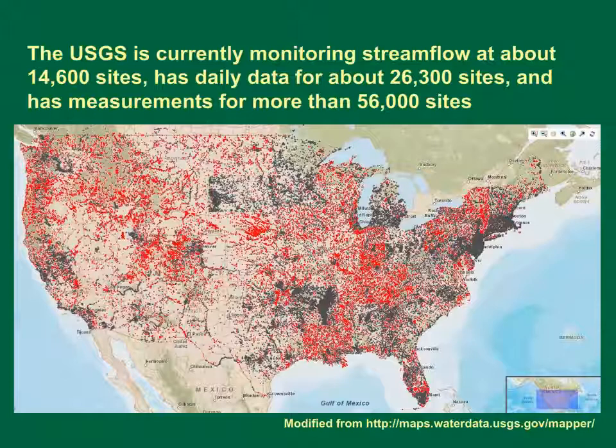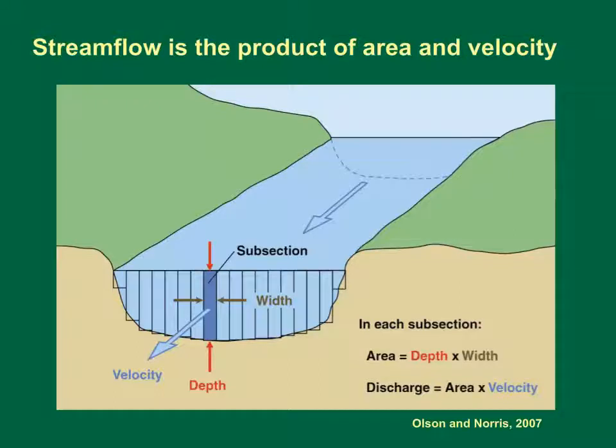The USGS uses stream stage measurements to estimate flows by using a relationship between stage and flow. At most sites, the monitoring station and the stage-discharge relation need constant maintenance by visiting hydrographers. This schematic diagram shows the method used to determine streamflow. The stream is divided into sections, and then the width, depth, and average velocity of each section is measured.